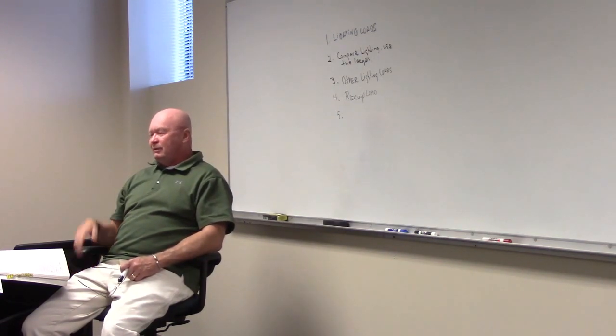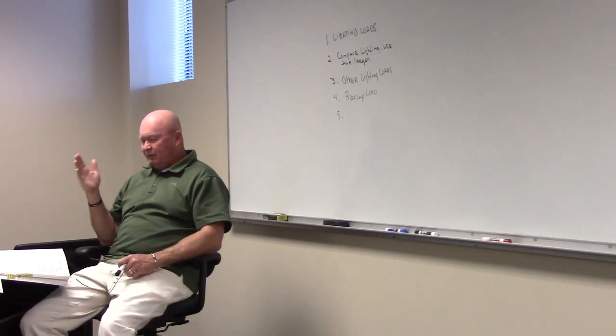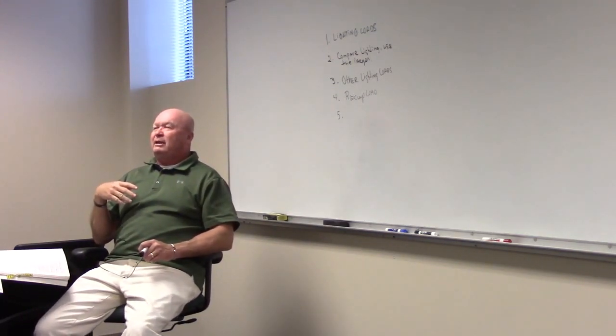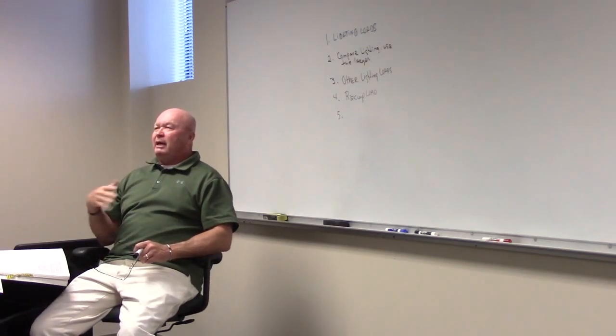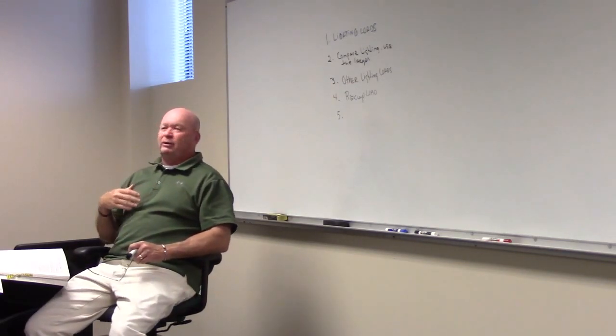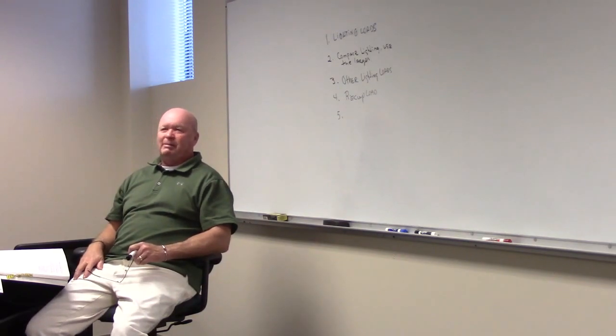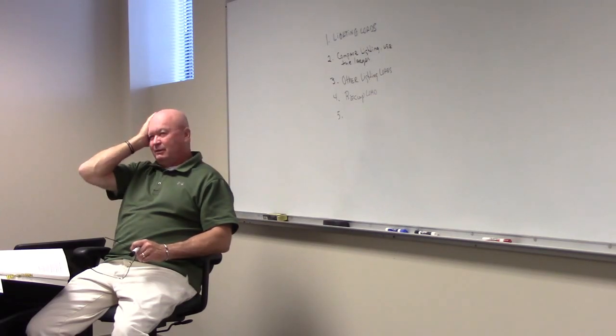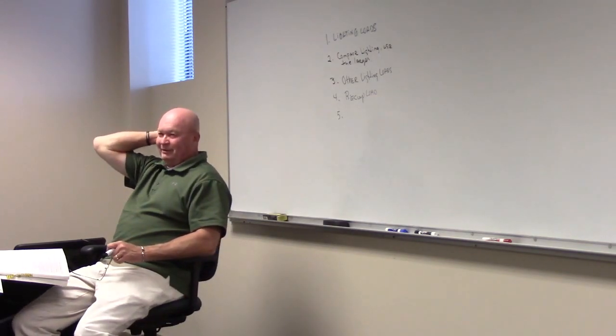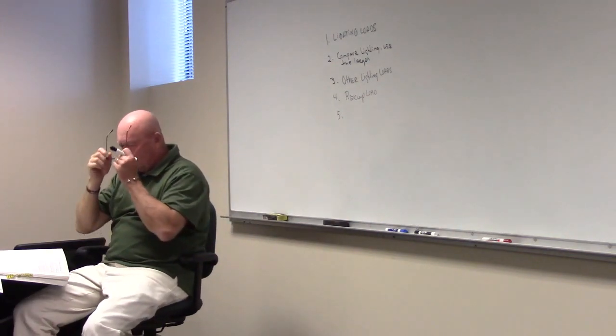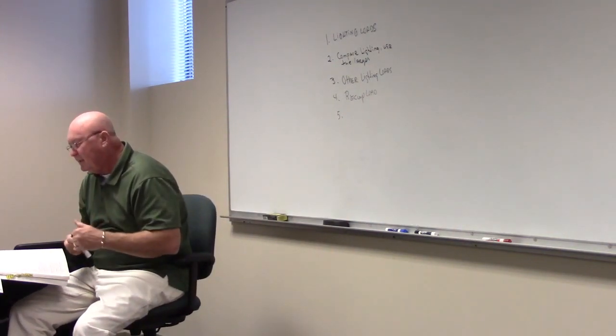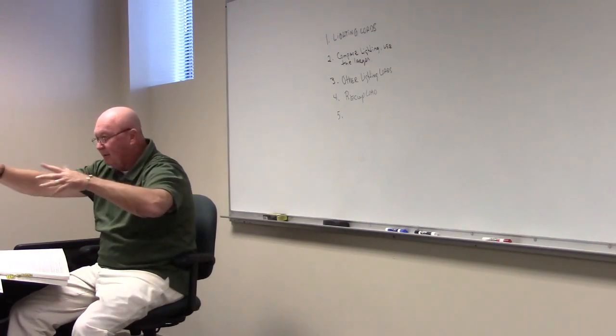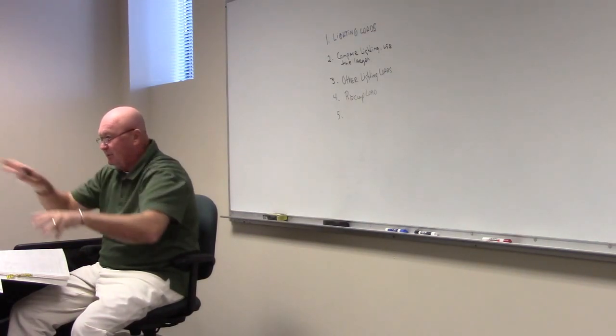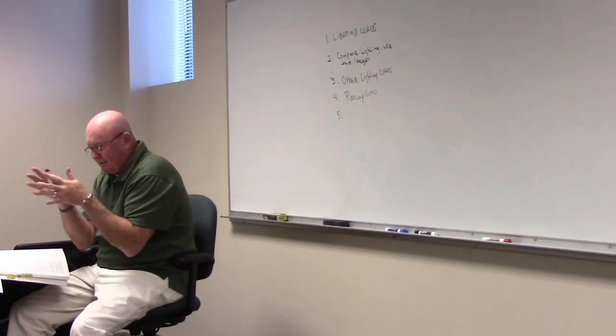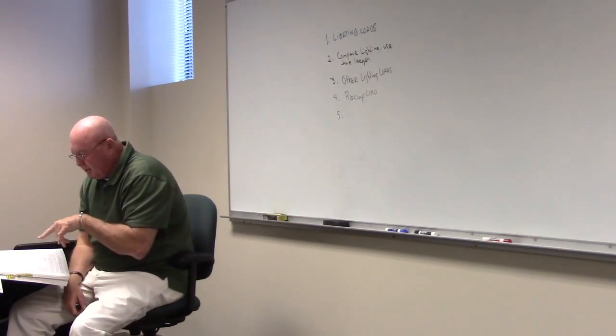So therefore, people with kids are exempt from that. But generally speaking, demand factor says, okay, in your house, Nate, it's just you and your wife, you're probably going to cut on 30% of your lights. Maybe. And you're probably pretty tight, so you probably got a candle you walk around with. You don't cut on any lights. Sometimes lightning bugs. Candles get expensive. That's right. So because of that, we have demand factors. He's one extreme and you're another, and so we've got to get in between here. And so there are some demand factors.